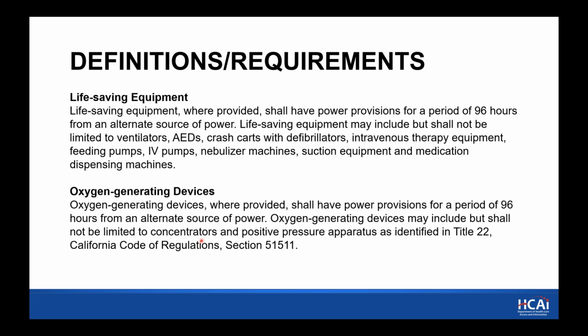So life safety equipment, where provided, shall have power provisions for a period of 96 hours from an alternate source of power. Life-saving equipment may include, but shall not be limited to, ventilators, AEDs, crash carts with defibrillators, intravenous therapy equipment, feeding pumps, IV pumps, nebulizer machines, suction equipment, and medication dispensing machines, to name a few. And oxygen generating devices have power provisions for 96 hours from an alternate source of power. Oxygen generating devices may include, but shall not be limited to, concentrators and positive pressure apparatus.